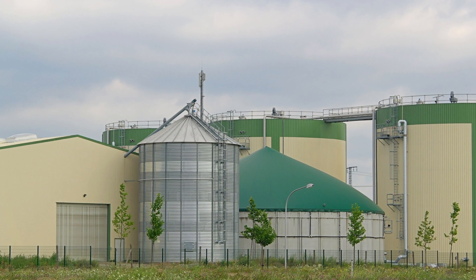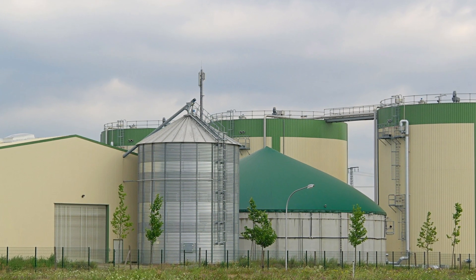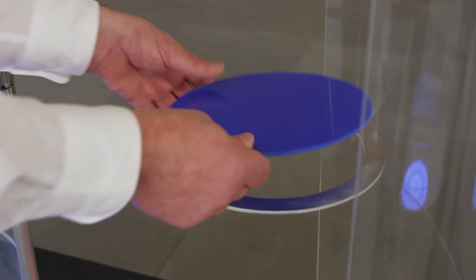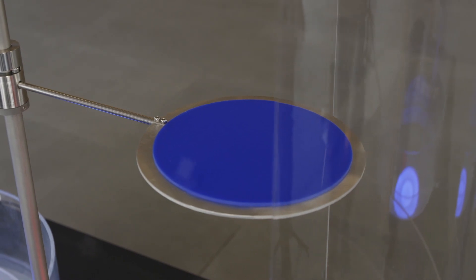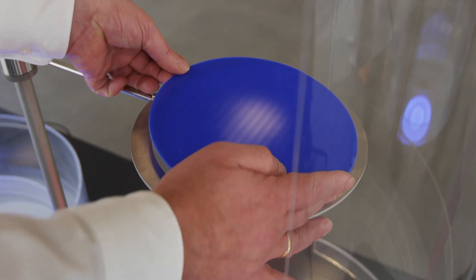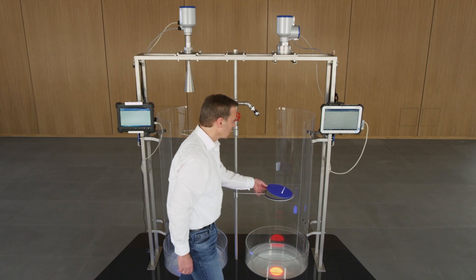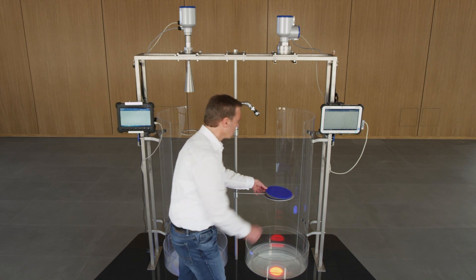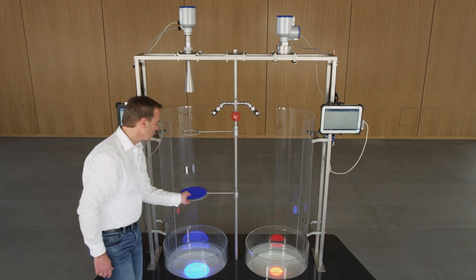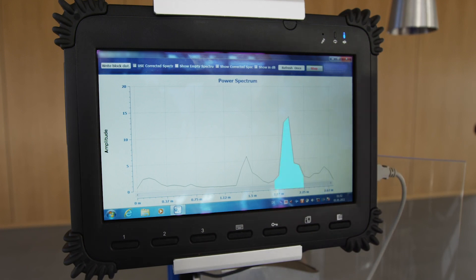In the case of plastic containers, it is also possible to realize the filling level measurement without modification of a tank, through the container casing. The plastic plate inserted here simulates the container cover. Behind the reflection of the plastic plate, the reflection of the water surface in the spectrum is clearly visible. The reflection of the plastic plate can be minimized by an oblique positioning, simulating, for example, an oblique tank roof. As expected, the 24 GHz system also shows comparable behavior — here also the reflection on the surface of the water is clearly visible, and the inclined position of the plastic plate also reduces the reflection on the simulated tank roof.